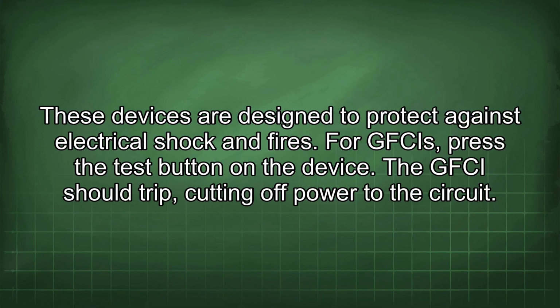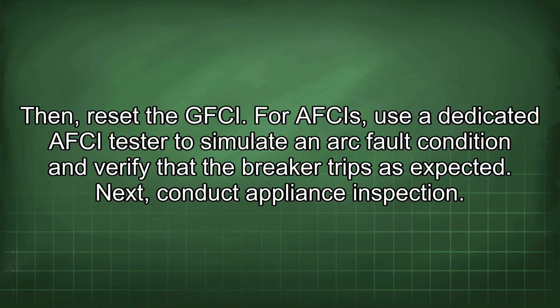For GFCIs, press the test button on the device. The GFCI should trip, cutting off power to the circuit. Then reset the GFCI. For AFCIs, use a dedicated AFCI tester to simulate an arc fault condition and verify that the breaker trips as expected.